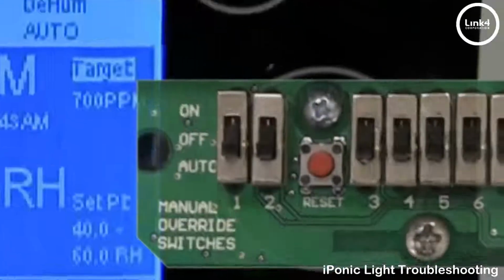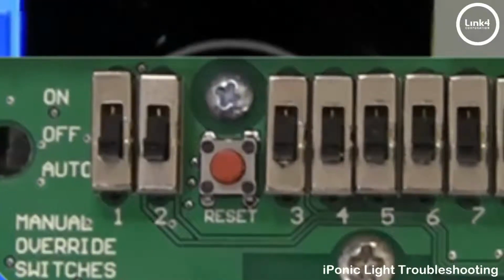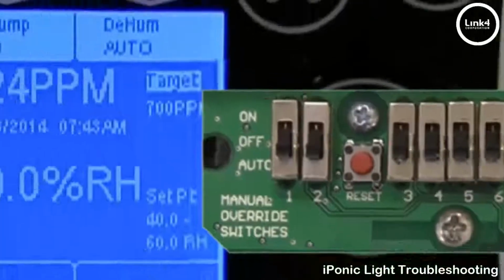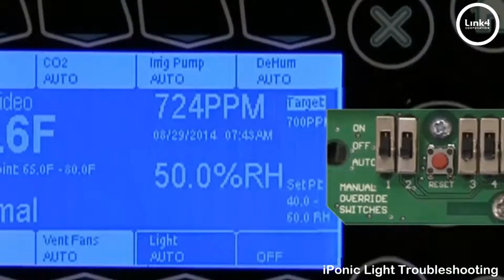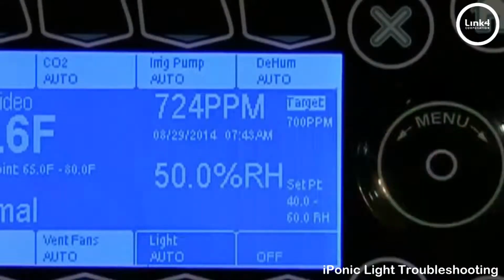Now, the last thing, the manual toggles on the back of the controller's printed circuit board, regardless of the front face programming, off, on, auto, timed override, whatever position that toggle is in, that's the state of this controller. So always make sure your manual toggles on the back are on auto.